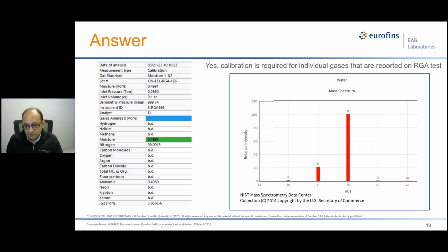And moisture, we calibrate for moisture every day, with a daily calibration prior to analysis. Now, this individual calibration gives me the calibration factor for that particular gas. But it is not only limited to that, it is also being used to actually quantify the interference and contribution to the other masses. I would like to show the example of moisture here.